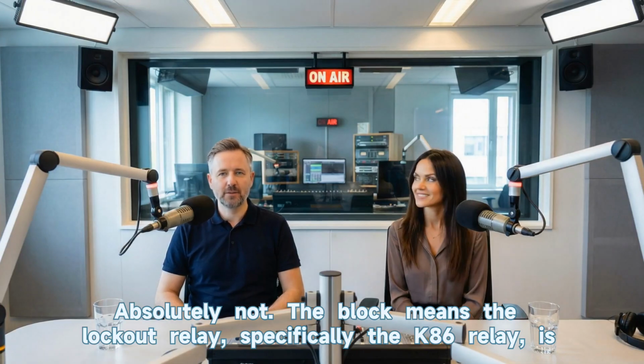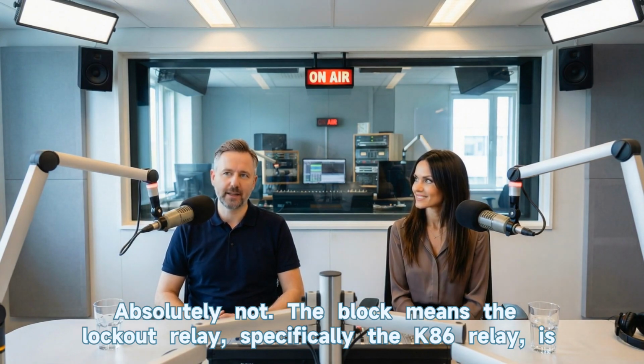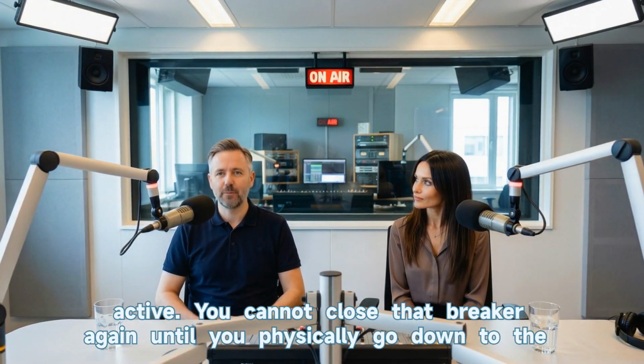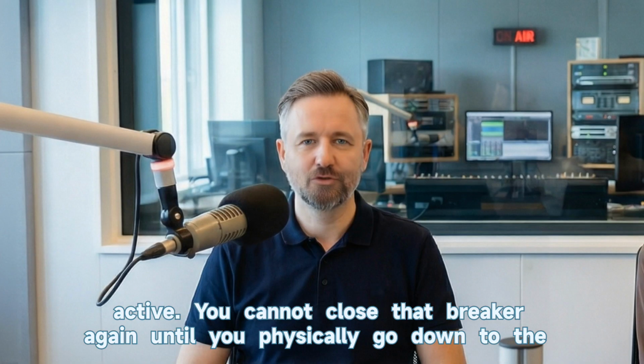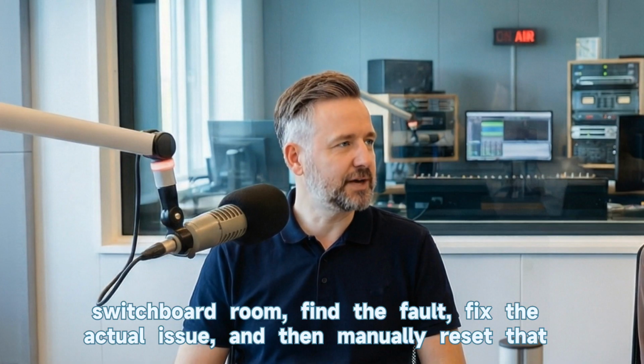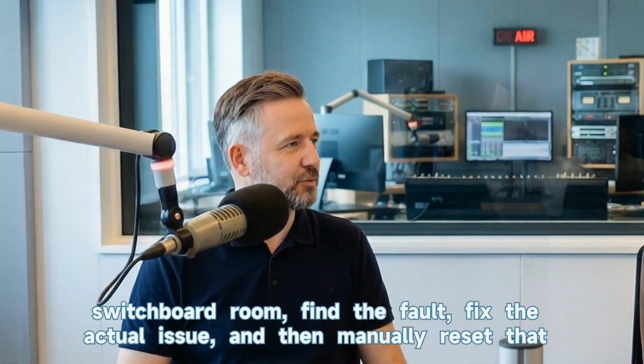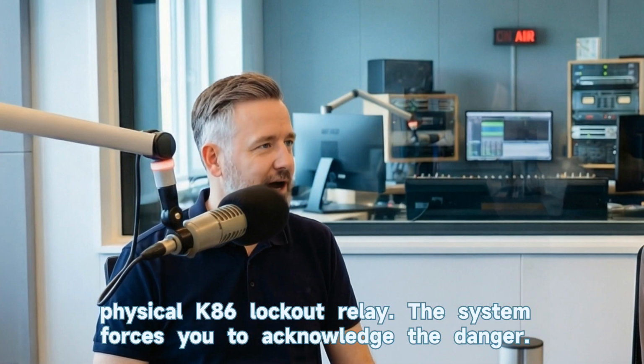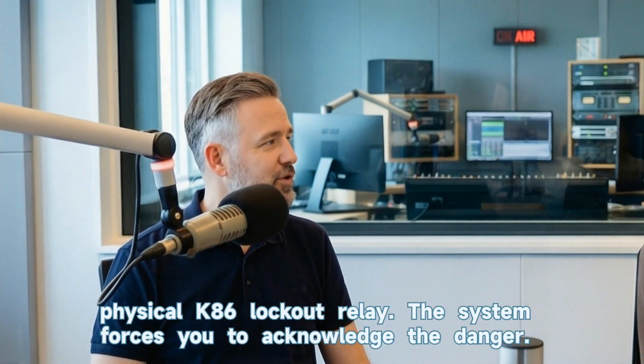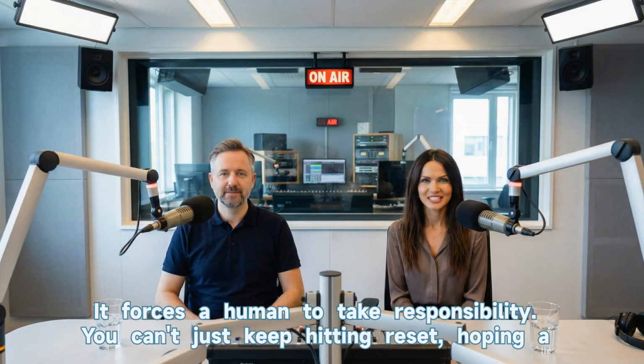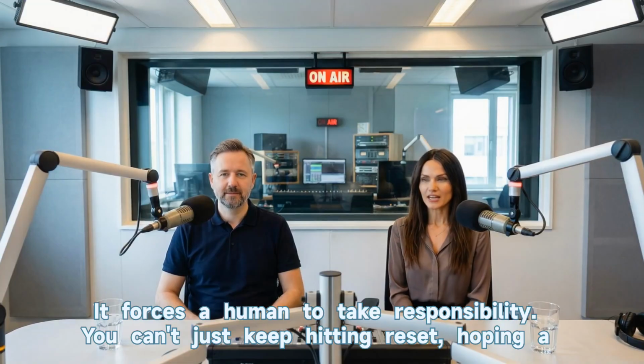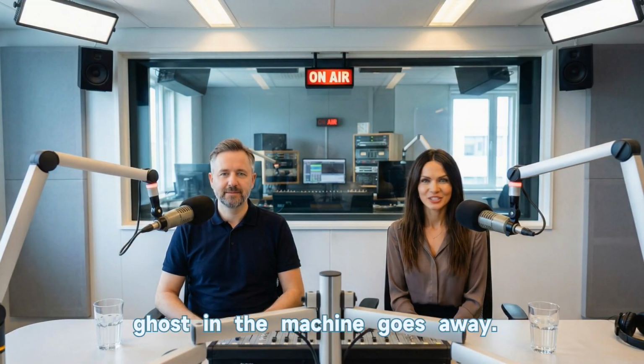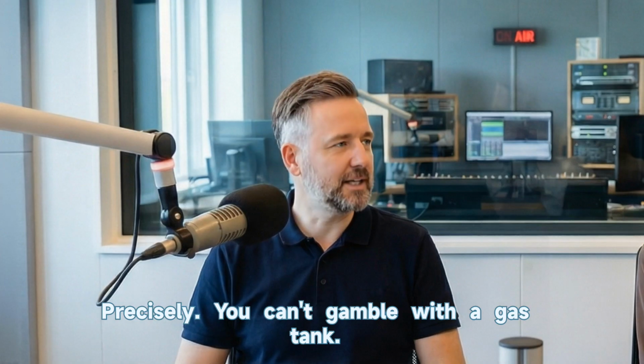Absolutely not. The block means the lockout relay, specifically the K86 relay, is active. You cannot close that breaker again until you physically go down to the switchboard room, find the fault, fix the actual issue, and then manually reset that physical K86 lockout relay. The system forces you to acknowledge the danger. It forces a human to take responsibility. You can't just keep hitting reset hoping a ghost in the machine goes away. Precisely. You can't gamble with a gas tank.